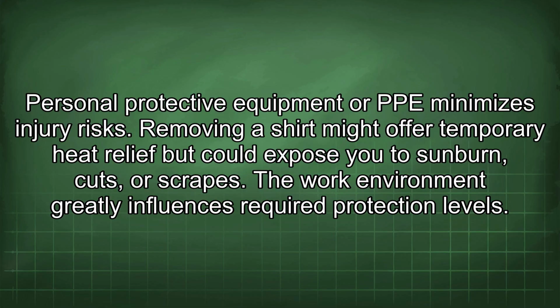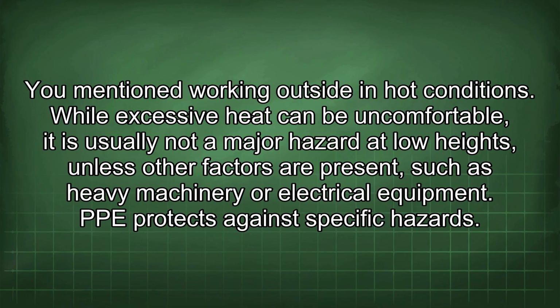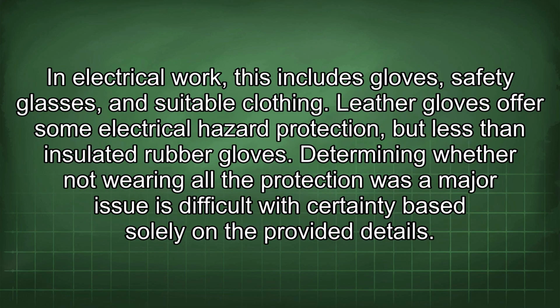The work environment greatly influences required protection levels. You mentioned working outside in hot conditions. While excessive heat can be uncomfortable, it is usually not a major hazard at low heights, unless other factors are present, such as heavy machinery or electrical equipment. PPE protects against specific hazards. In electrical work, this includes gloves, safety glasses, and suitable clothing. Leather gloves offer some electrical hazard protection, but less than insulated rubber gloves.